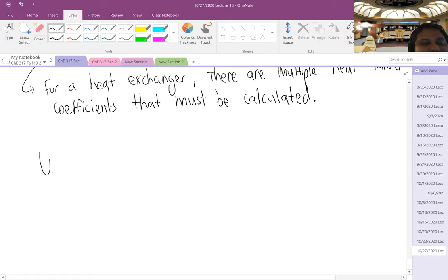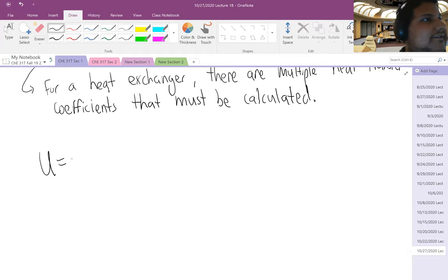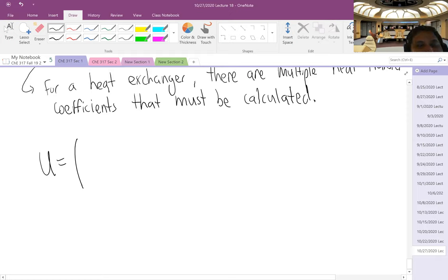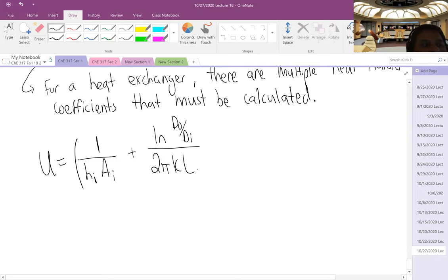So we can calculate U, to be honest, one of many, many, severally different, confusing, and complicated ways. I will give you a few that I think will be sufficient to make reasonable calculations.